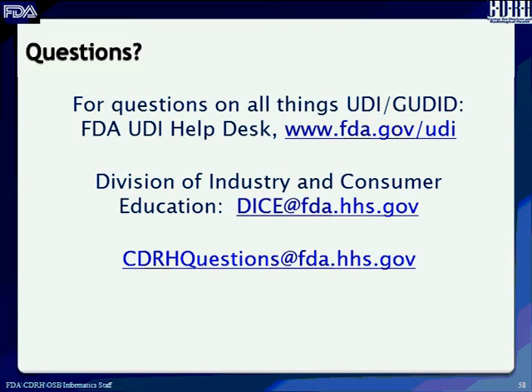So I have a following question that's just general. If we are going to include a UDI label on a product that we are not selling on its own, do we still have to provide all these characteristics and GUDID attributes and enter them in the GUDID? I guess if it's a finished device, then yes. If it's a finished device that is suitable for use or capable of functioning by itself, then yes, you would need to have the UDI based on the final rule.